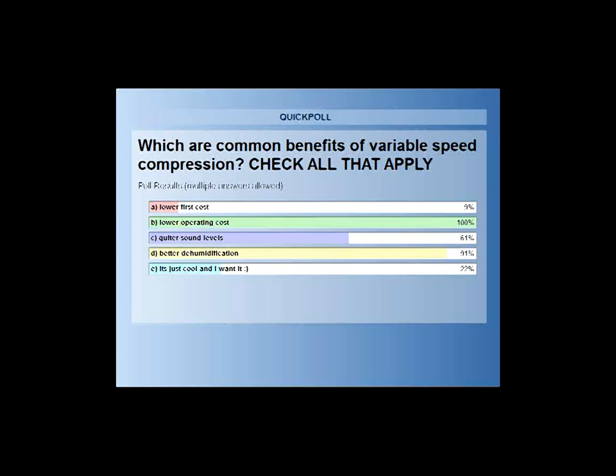Pretty much every answer, well, B, C, and D are all correct. E is a preference, right? So there's no right or wrong there. A is the only wrong answer. It's probably not going to have a lower first cost than any traditional systems. But it's very likely it's going to have a lower operating cost, and certainly a lower operating cost than other heat pumps. It's going to typically be quieter because other things are ramping down. It's definitely going to have better dehumidification, and sometimes people just want stuff because it's cool.